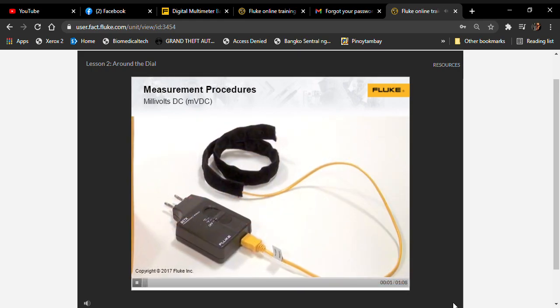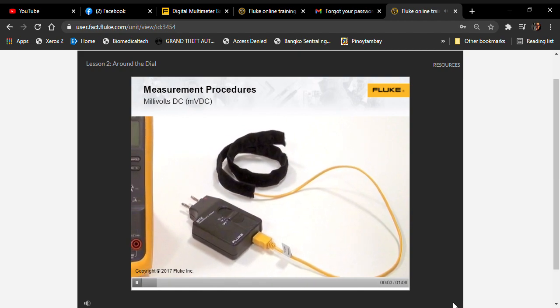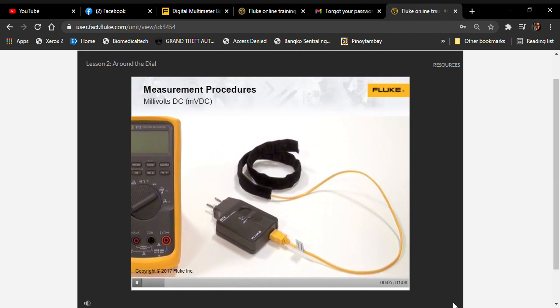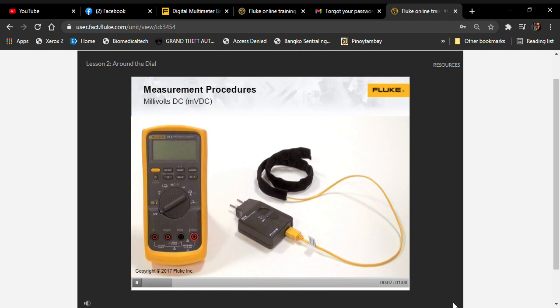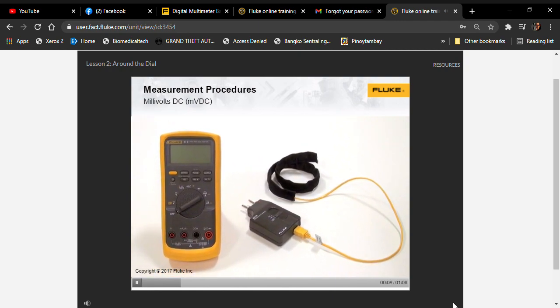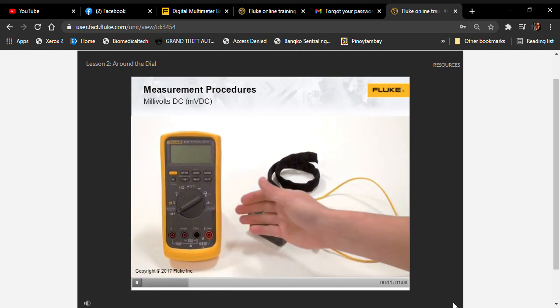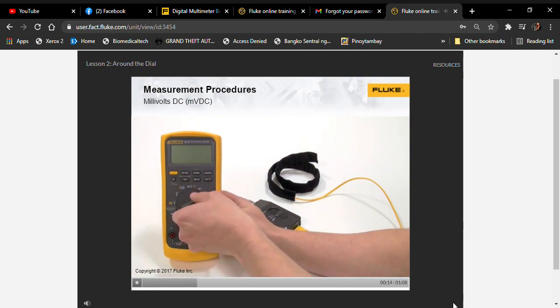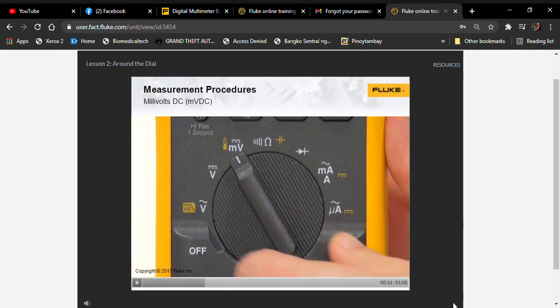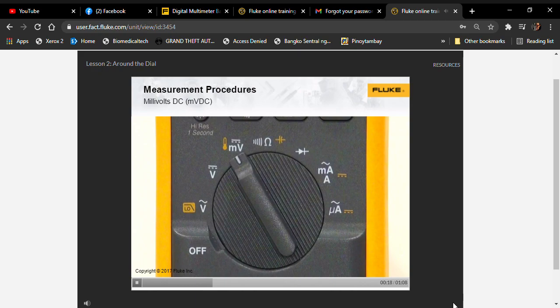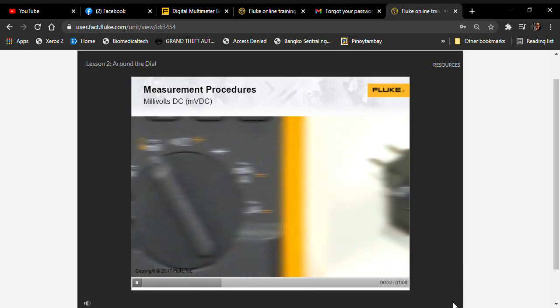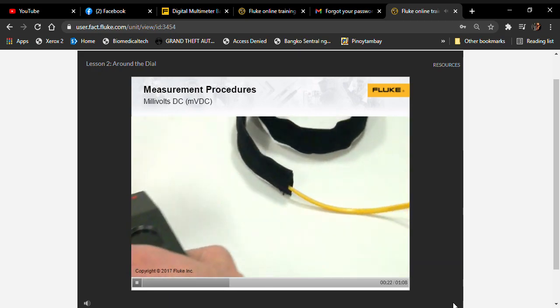In this procedure for measuring millivolts DC, we'll be using a plug-in temperature accessory. To set up the multimeter to measure millivolts DC, the selector switch is first moved to the millivolts DC voltage position. It's indicated with an MV topped by the DC symbol. Then the accessory is plugged into the multimeter's input jacks.